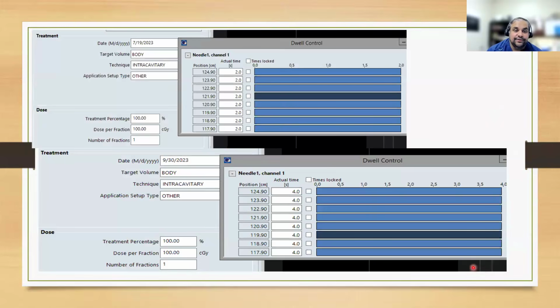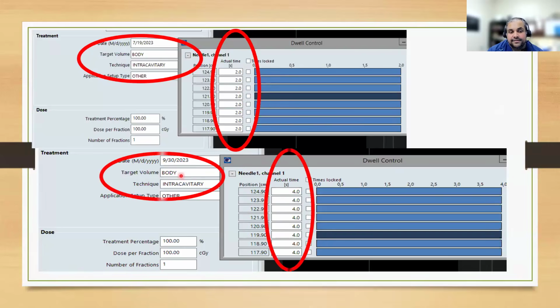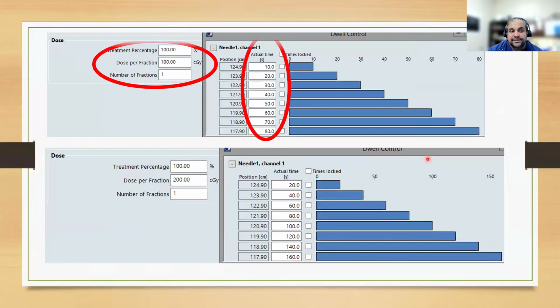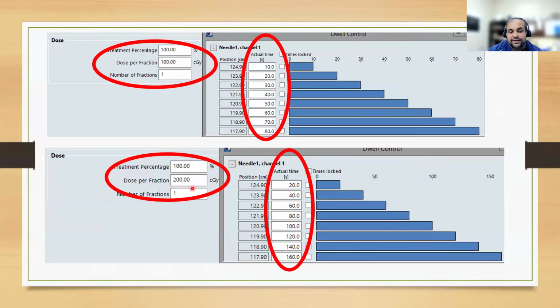One simple test you can do within your clinic is, say you did a test, in this case, on the 19th of July, and you just gave a dwell time of 2 seconds. After about 73 days, your dwell time should automatically double. Similarly, if your dose is 100 centigray per fraction and you change it to 200, your dwell time should also double.